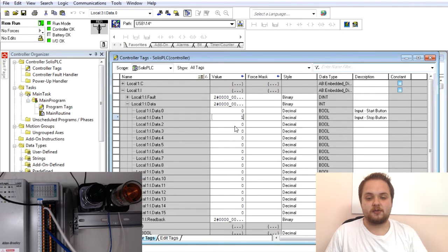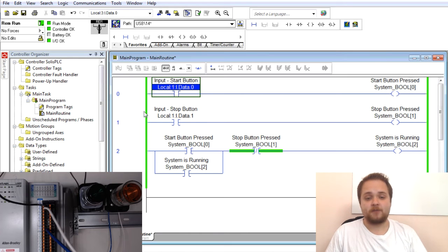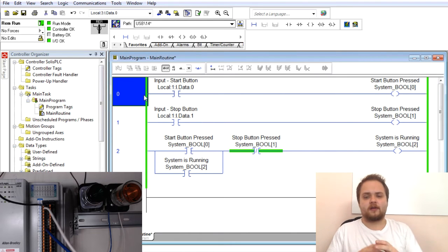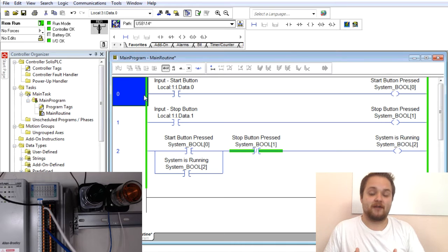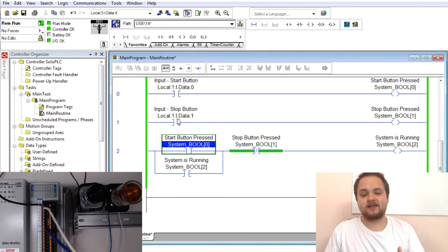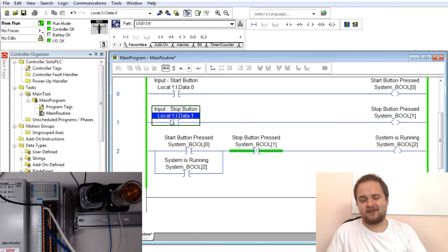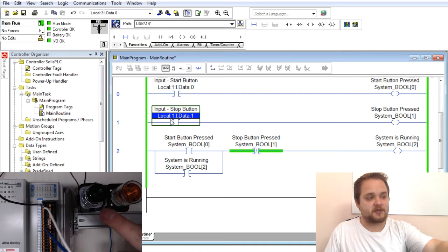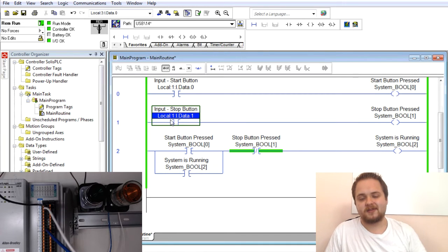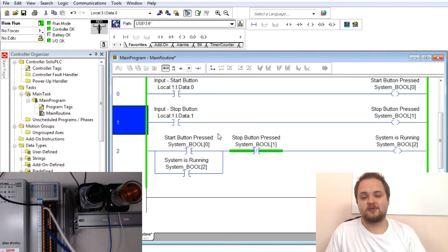And of course, this is an input, so it's only evaluating based on what the card is coming in as. Now, the other point that I want you to drive home is that the XIC does not necessarily only need to tie into buttons. Your buttons, or your inputs, your sensors, whatever's coming into the PLC, are the most obvious thing to use an XIC and XIO on. However, they can be used on internal tags.